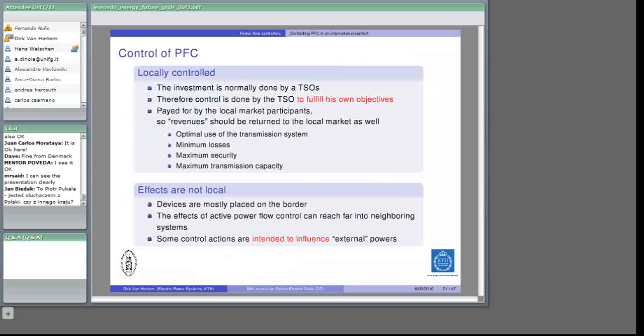However, although you are installing these devices in your own system, they have effects that are not local. As you could see from the picture before, the devices are mostly placed on the border, and the effects reach far into the neighboring systems. Most of the devices are even intended to influence external power flows. For instance, the power flow controlling devices in Belgium limit the flow that goes from the north of Germany to the south of Germany, where loop flows were happening because of the increased generation of wind.